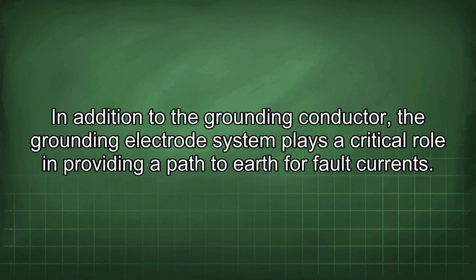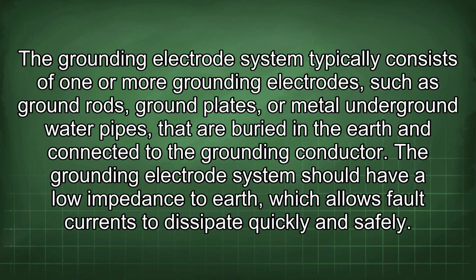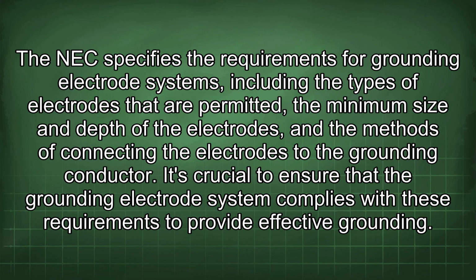In addition to the grounding conductor, the grounding electrode system plays a critical role in providing a path to earth for fault currents. The grounding electrode system typically consists of one or more grounding electrodes, such as ground rods, ground plates, or metal underground water pipes, that are buried in the earth and connected to the grounding conductor. The grounding electrode system should have a low impedance to earth, which allows fault currents to dissipate quickly and safely. The NEC specifies the requirements for grounding electrode systems, including the types of electrodes that are permitted, the minimum size and depth of the electrodes, and the methods of connecting the electrodes to the grounding conductor. It's crucial to ensure that the grounding electrode system complies with these requirements to provide effective grounding.